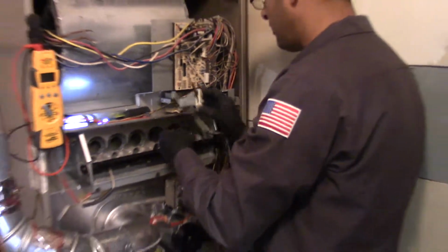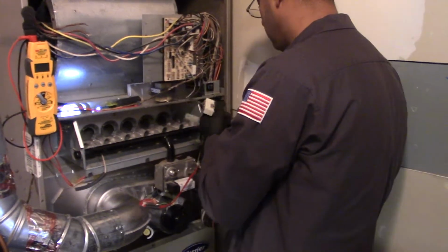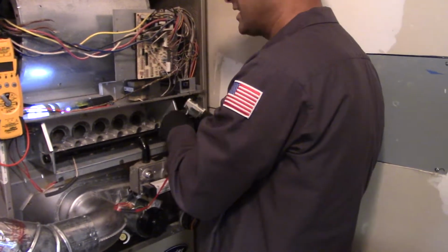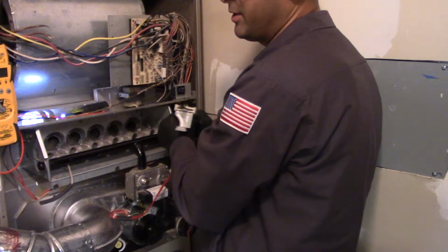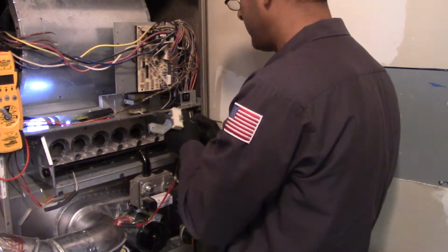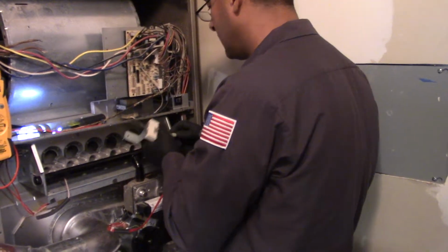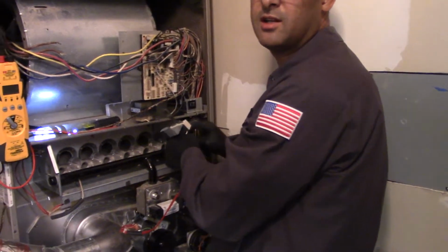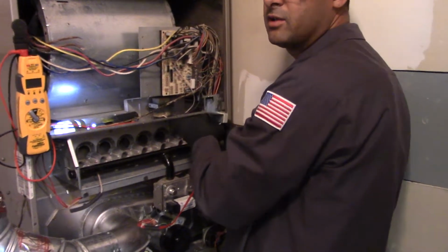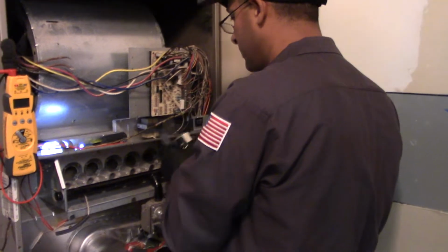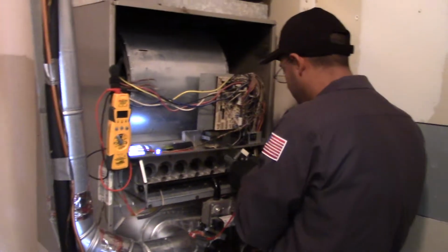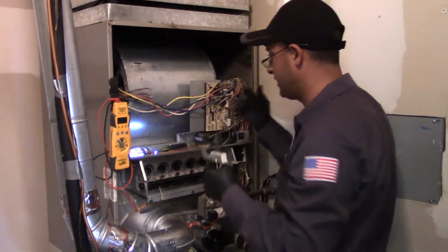So let me go ahead and disconnect that, because every igniter actually has a reading you need to check, and it's going to be different for different manufacturers and different igniters. There are charts online that give you the readings, and what we're looking for is resistance in the actual igniter, which we'll read with our meter. So be careful with that.